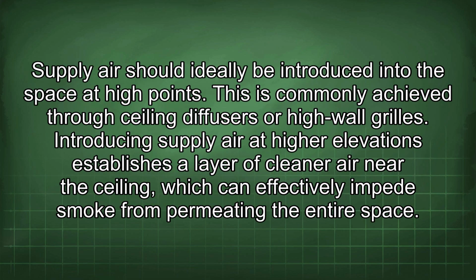Supply air should ideally be introduced into the space at high points. This is commonly achieved through ceiling diffusers or high wall grills. Introducing supply air at higher elevations establishes a layer of cleaner air near the ceiling, which can effectively impede smoke from permeating the entire space.